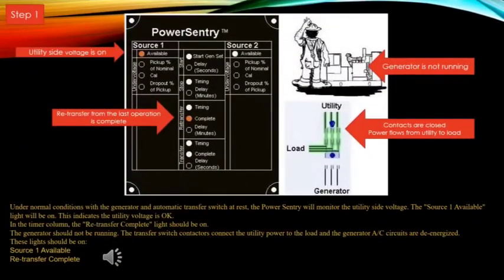Step 1: Under normal conditions with the generator and automatic transfer switch at rest, the power sentry will monitor the utility side voltage. The source one available light will be on, indicating the utility voltage is okay. In the timer column, the re-transfer complete light should be on. The generator should not be running. The transfer switch contactors connect utility power to the load and the generator AC circuits are de-energized.